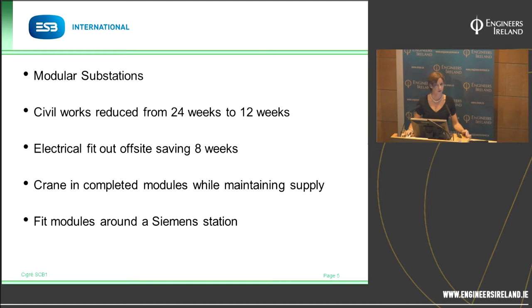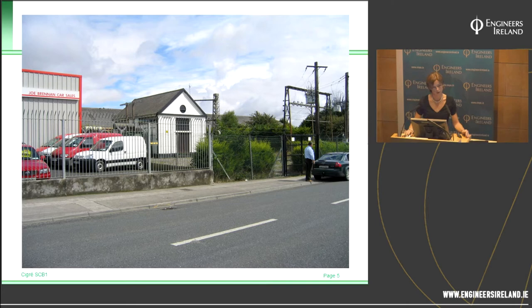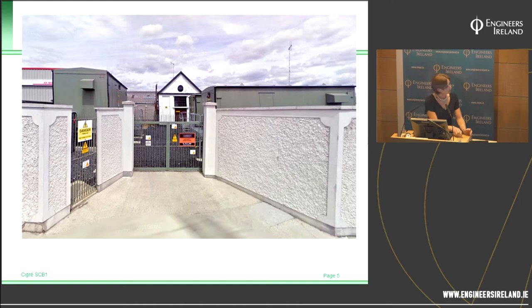That's a picture of a 38 kV station in Carlow. You can see it's on the main road there, and it's surrounded on the other three sides by local businesses. And that's it with its modules installed. And what you can't see is behind these two modules on the right-hand side are two new 10 MVA power transformers. And we wrote a little bit in our paper about how we got these in position. And in this case, we had a road closing license one Sunday morning in the summer. It was about 5 o'clock. And we lifted in the three modules and the two transformers in the space of a few hours.